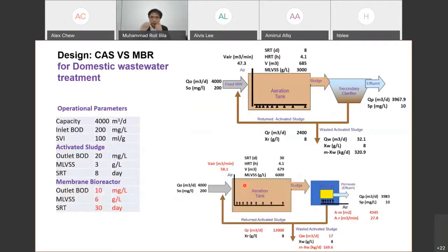So now here I have the same feed wastewater when I designed this one. First focus on the left here. These are the operational conditions of my feed. Okay, this slide is an example for domestic wastewater. So let's say we have a capacity of 4,000 cubic meters per day. Inlet BOD is 200 milligrams per liter. And let's say this is the ideal sludge condition. Our sludge volume index is 100 milliliters per gram.